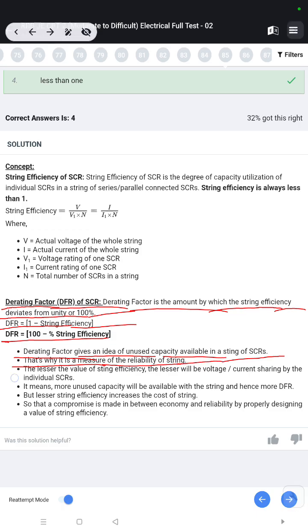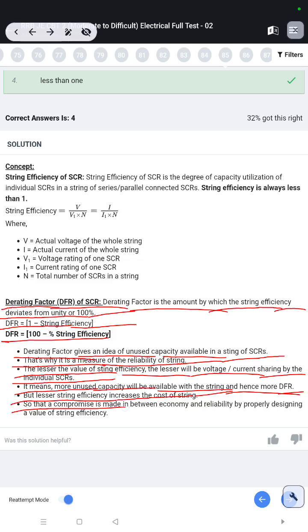The lesser the value of string efficiency, the lesser will be voltage current sharing by individual SCRs. It means more unused capacity will be available with the string and hence more DFR. But lesser string efficiency increases the cost of string, so that a compromise is made in between economy and reliability by properly designing a value of string efficiency.